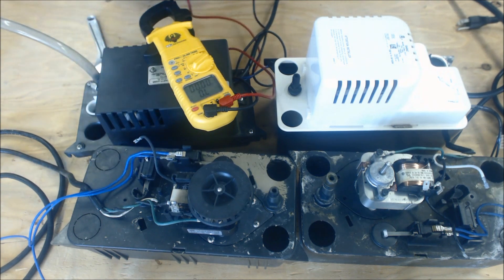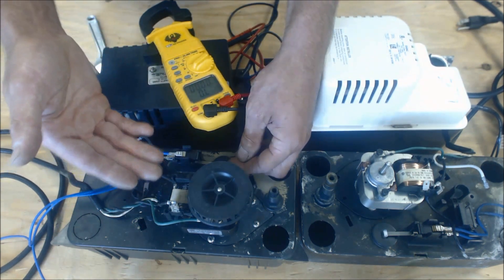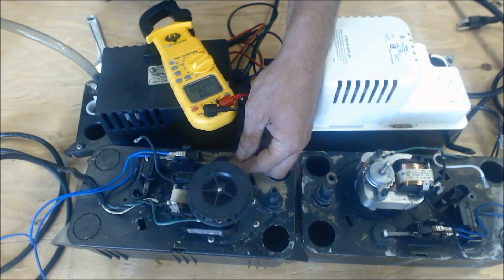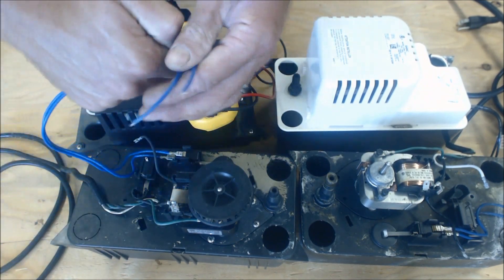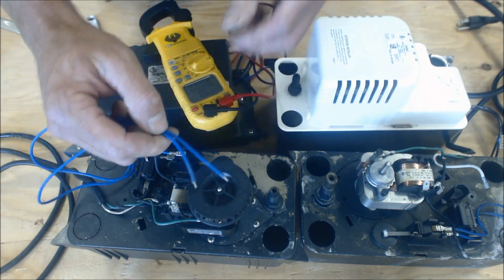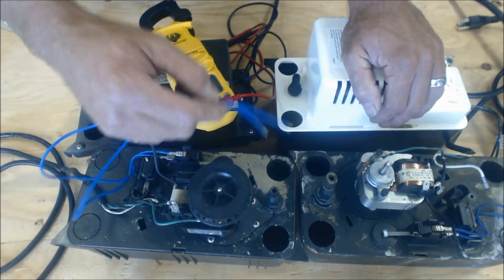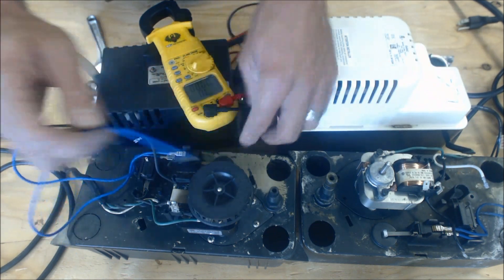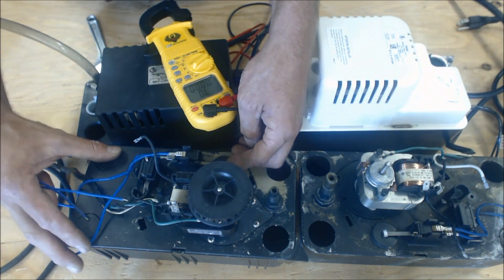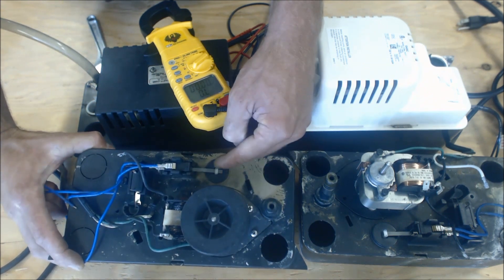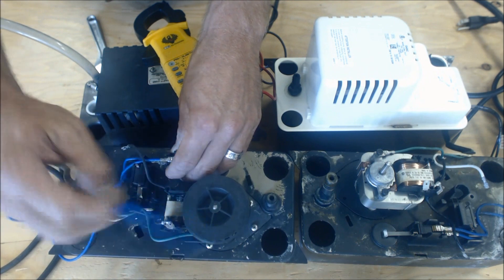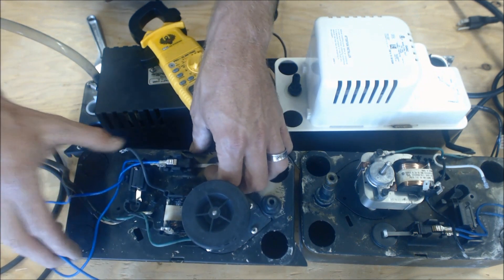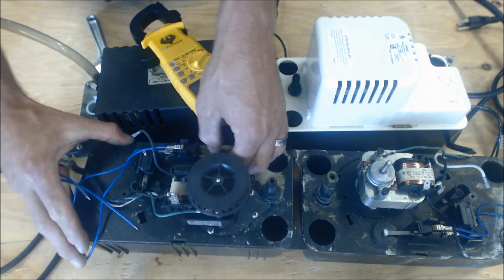This switch is actually your high water cutoff. So if the pump is not running or it's not plugged in or something like that, this is to shut off your wire or your red wire. Basically what it's doing is it's opening the electrical circuit. So when this is down right here, when this is down, these wires right here are closed. When this is up, these are open. It's breaking the electrical circuit.